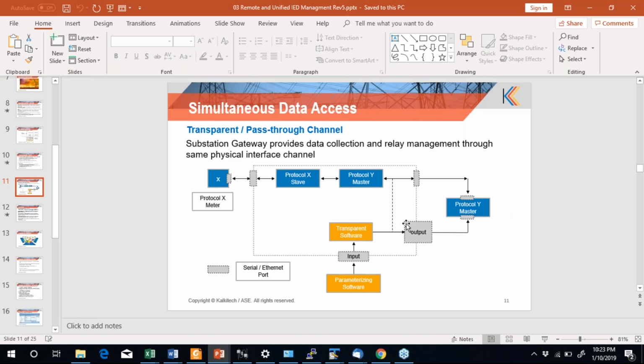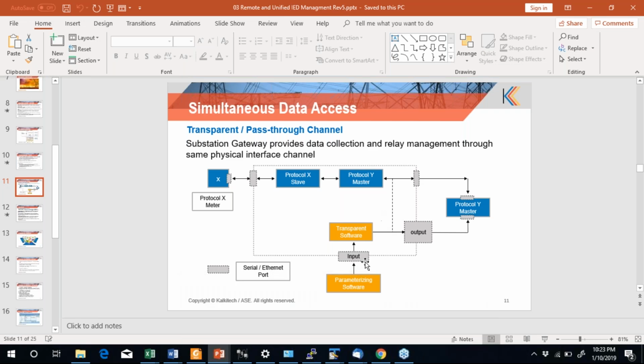So these are two mechanisms, but most utilities prefer the transparent channel having the highest priority method, because configuration happens very rarely, and when it happens, they are okay with temporarily halting the main channel and letting the configuration complete fully before processing the main channel.